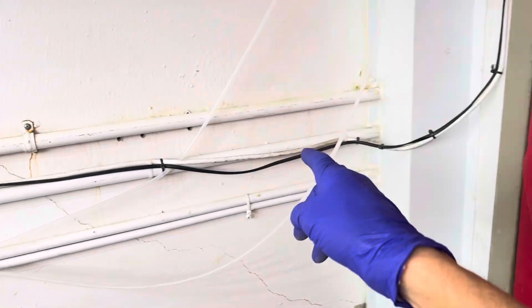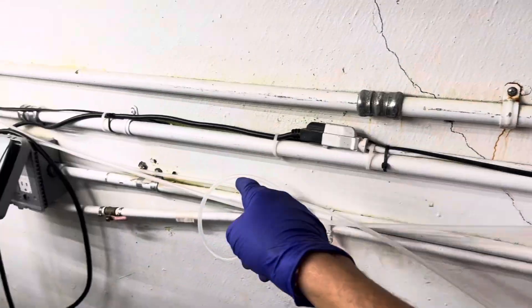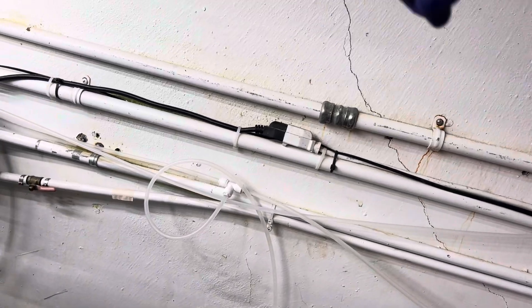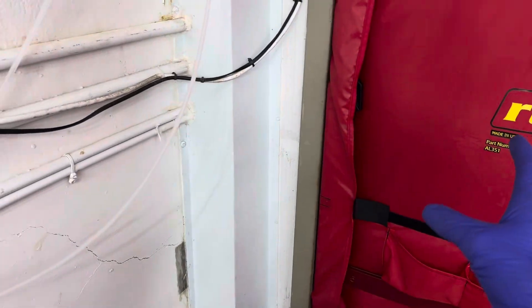We also find that the conduit for the electrical is all cold because if the room is negative and pulling air, there's air wanting to be pulled in when the door is closed.